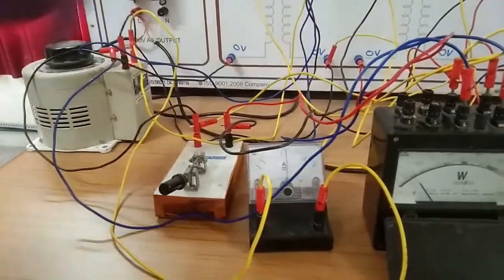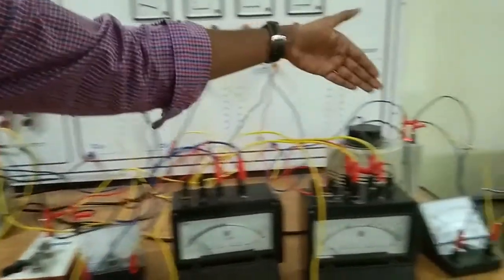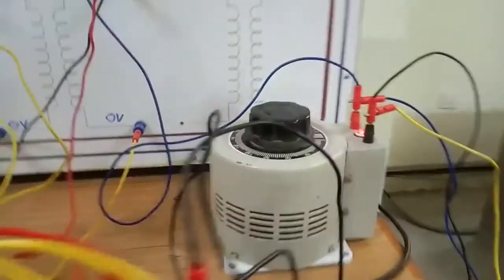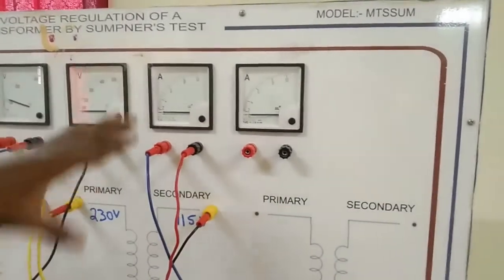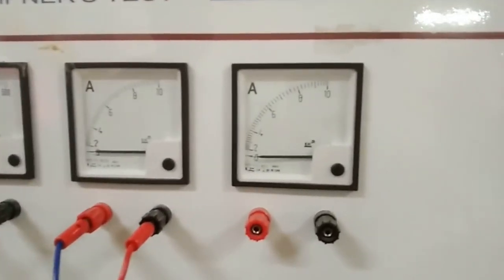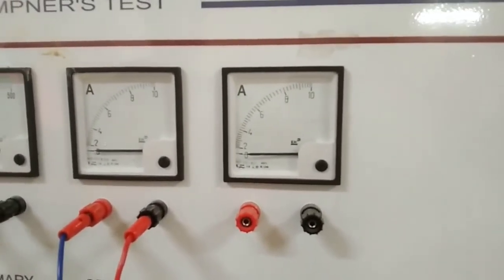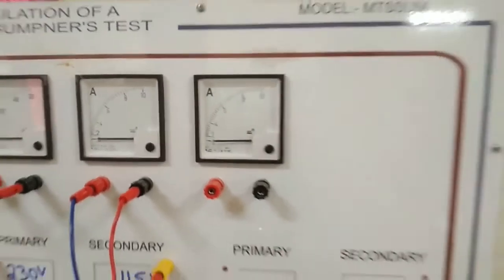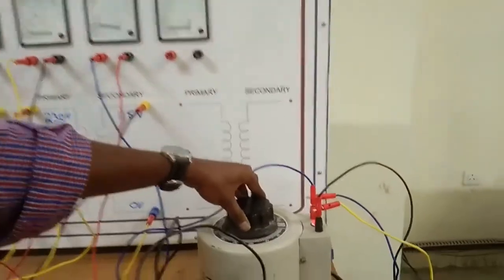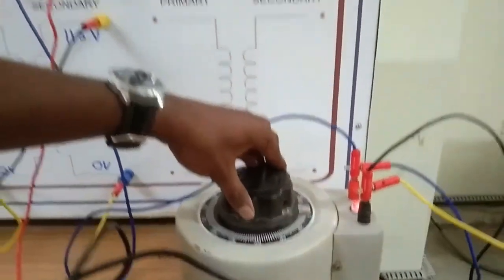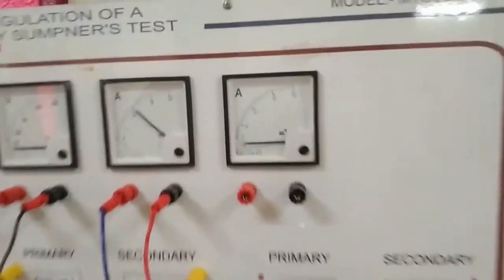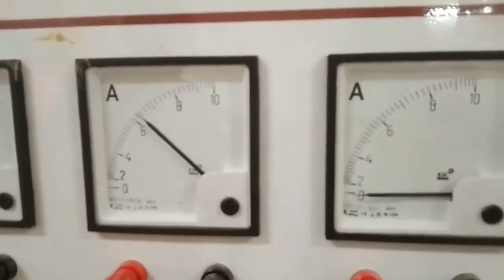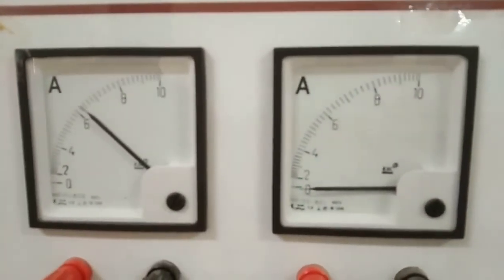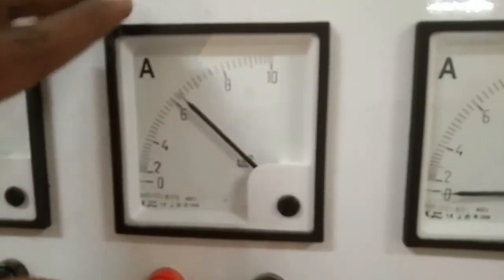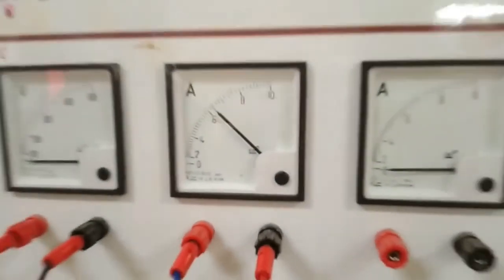Now with the help of the secondary auto transformer, we need to adjust so that the rated current flows through this ammeter, right? As per the nameplate, it is a 2 kVA transformer. With the help of the nameplate, if you calculate, the rated current may be 6.8 amperes. So I need to vary this secondary auto transformer in such a way that the ammeter displays 6.8 amperes, right? Then when this ammeter displays 6.8, that should be rated. Then we need to note down all the meter readings.